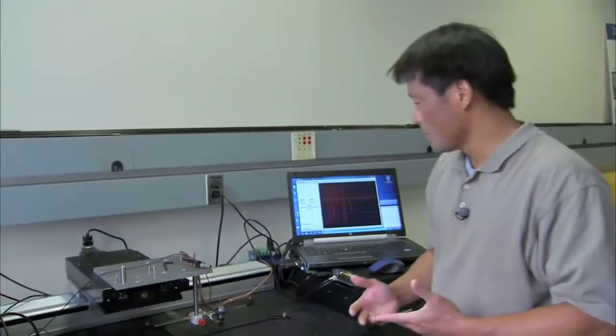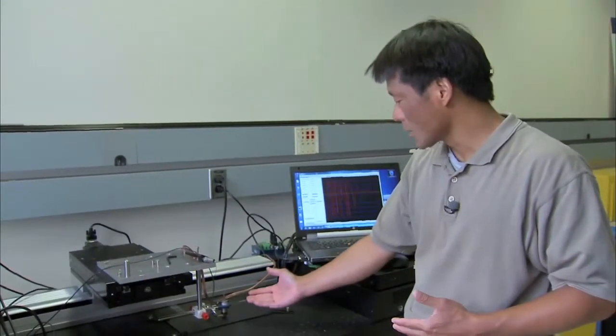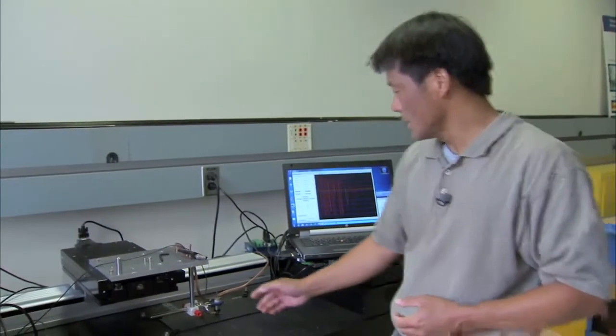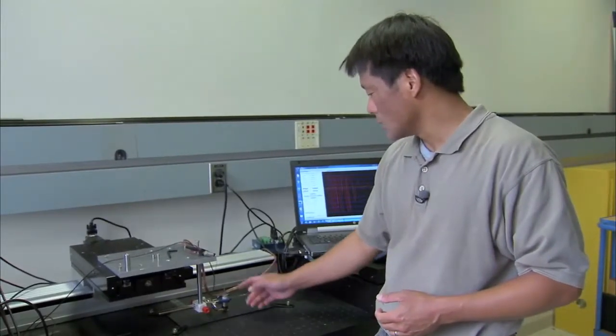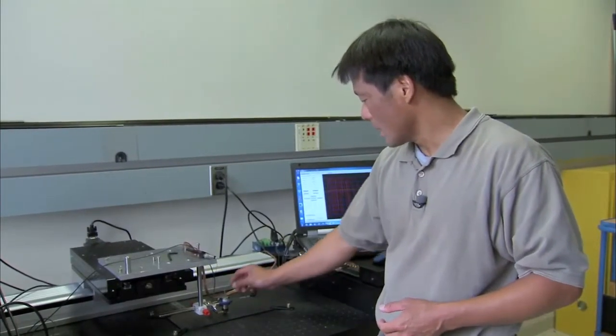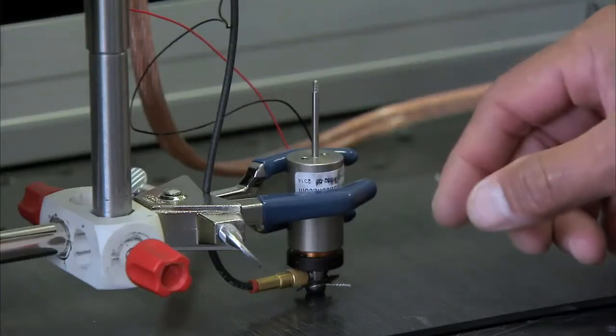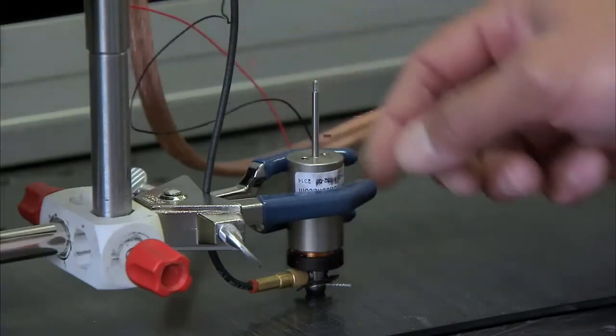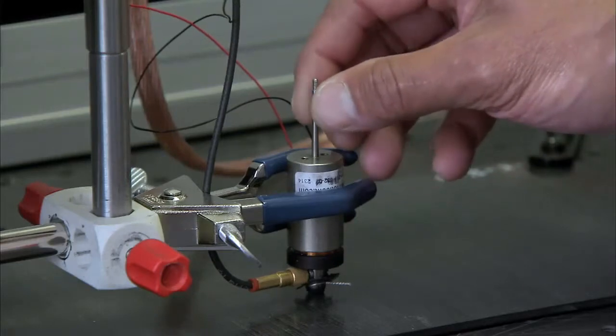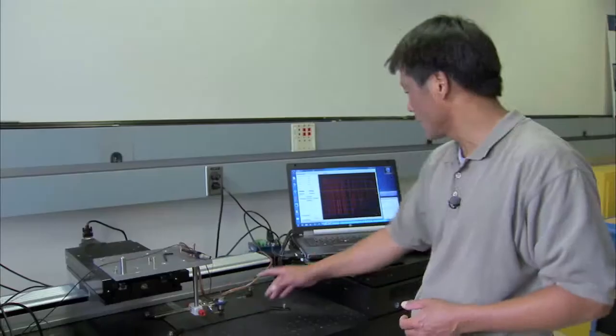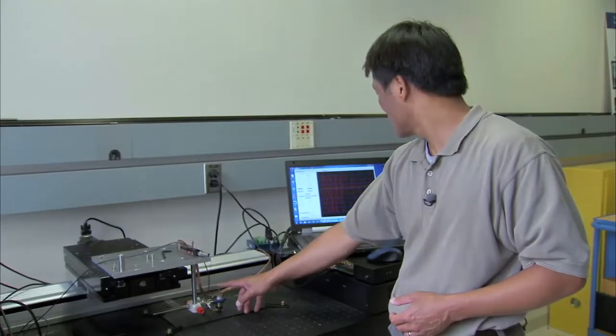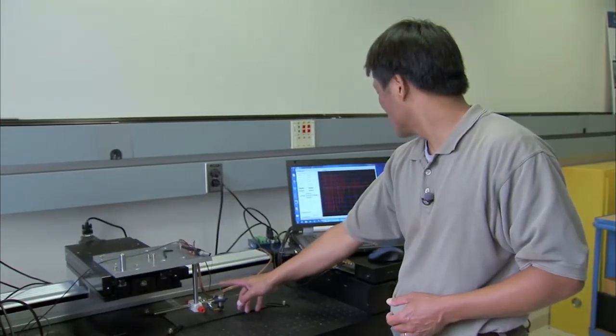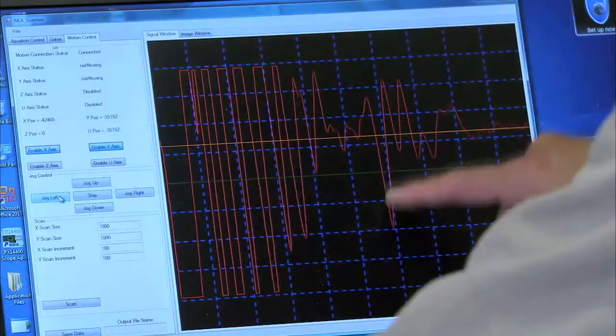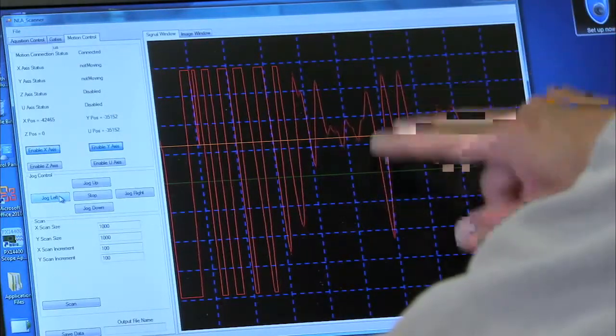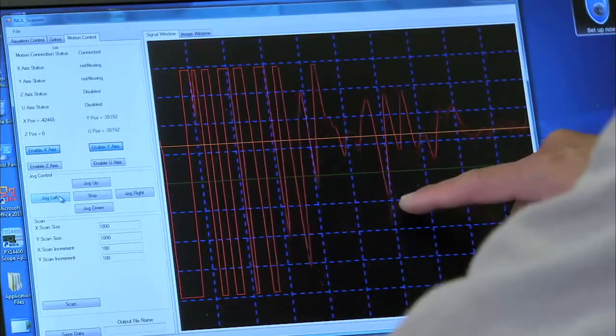So now we have the transducer with the solid couplant membrane mounted to a voice coil motor, and what that does is apply slight pressure, because it has a magnet in the coil. As I send electrical current to the motor, it can move up and down. And as you can see on the screen, as I slightly push down, you can see the signal here, which is the back surface of the composite sample that I'm inspecting.